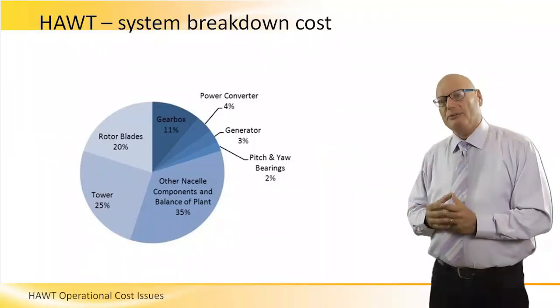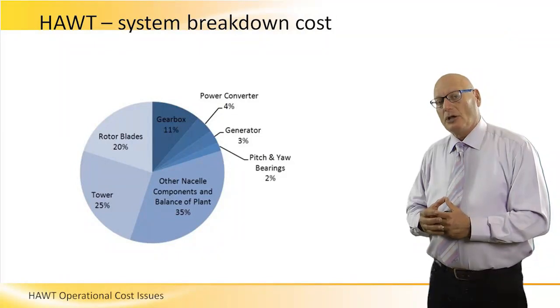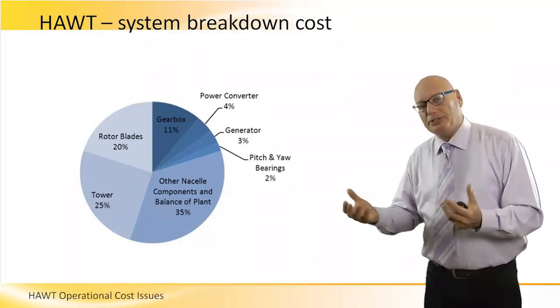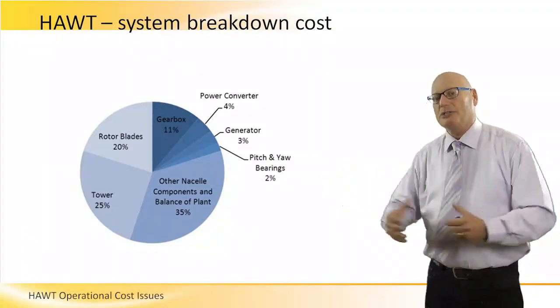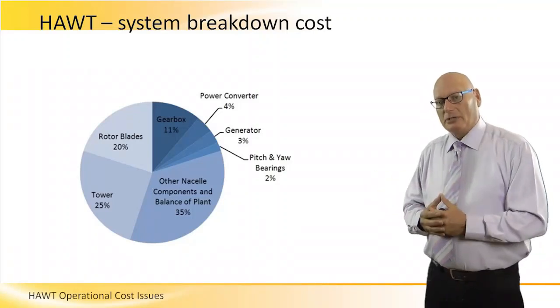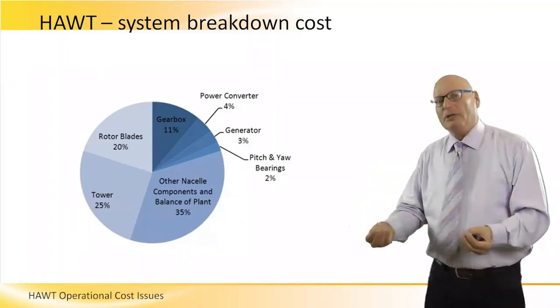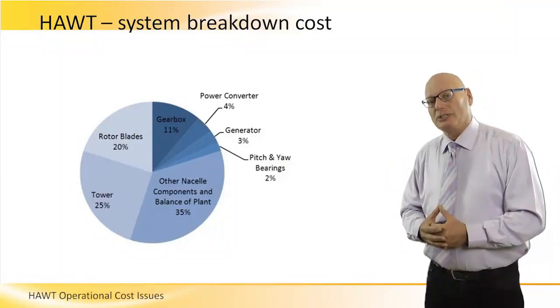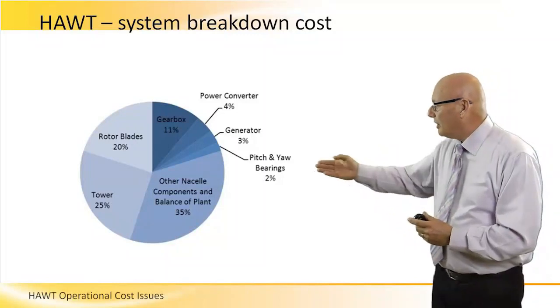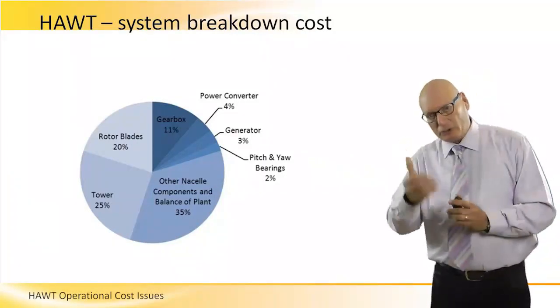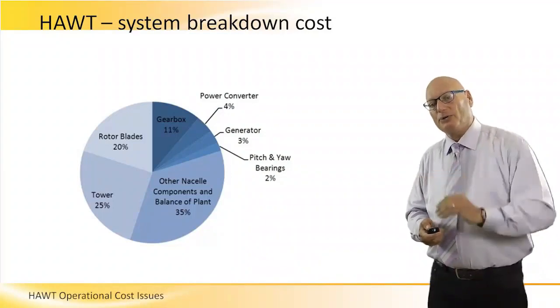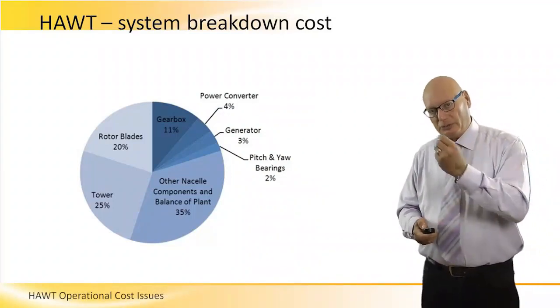The gearbox itself is 11% of breakdown cost. In large HAWT farms the gearbox is a huge machine, and when it breaks down it's very costly to repair. The power converter is only 4%. Pitch and yaw bearings and control is 2% — minor. Rotor, tower, and nacelle components are the majority of the breakdown cost.